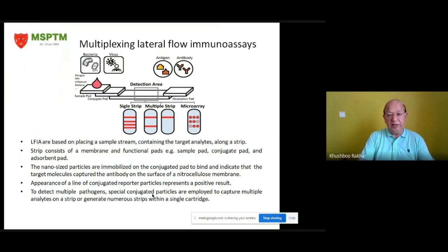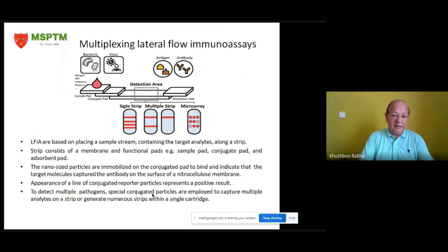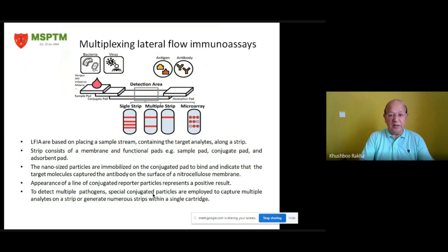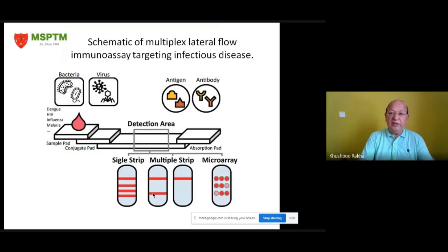Multiplexing lateral flow immunoassays are based on placing a sample stream containing target analytes along a strip. The strip consists of a membrane and functional pads — sample pad, conjugate pad, and absorbent pad. Nano-size particles are immobilized on the conjugate pad to bind and indicate target molecules captured by antibody on the surface of a nitrocellulose membrane. Appearance of a line of conjugated reporter particles represents a positive result. To detect multiple pathogens, special conjugated particles capture multiple analytes on a strip or generate numerous strips within a single cartridge. This schematic of multiplex LFIA targeting infectious diseases — including dengue, HIV, influenza, and malaria — is shown and explained here.